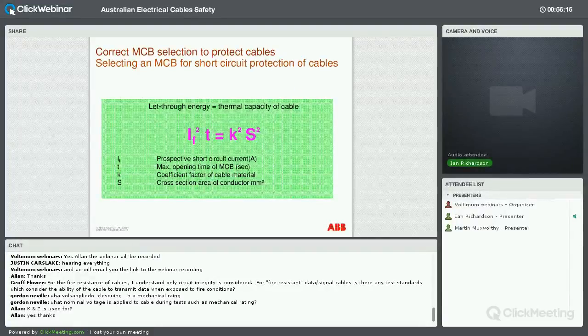When we get to short circuit values, it's a very similar theory, except there's a slightly different formula here. Looking at our I²T type values, we're actually looking at an energy value which is being pumped into that cable, which also will have a heating effect. Because with a short circuit, we're looking at an extremely high level of temperature which is trying to be thrown into that cable. It means that our breaker has to operate at a very, very fast time.